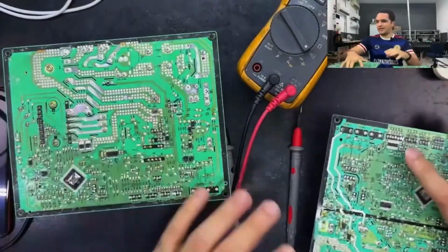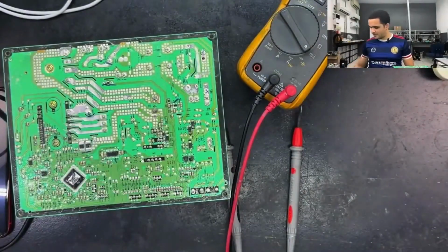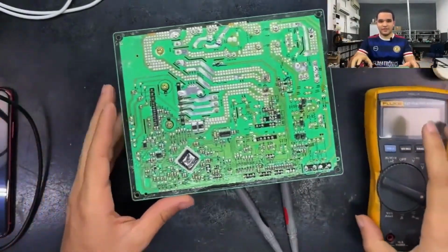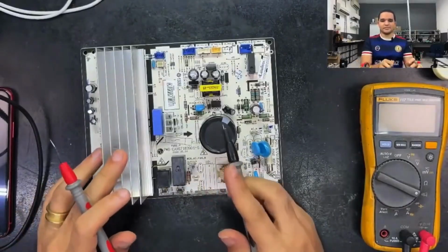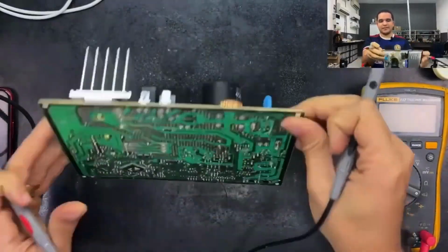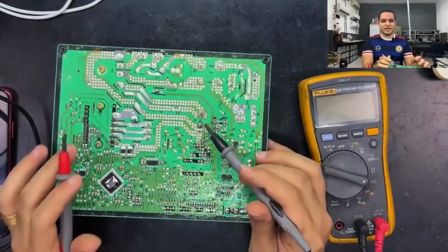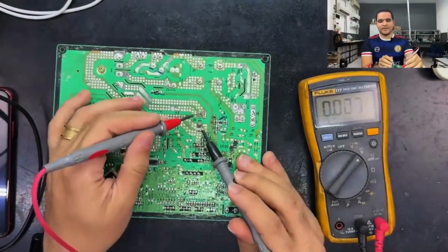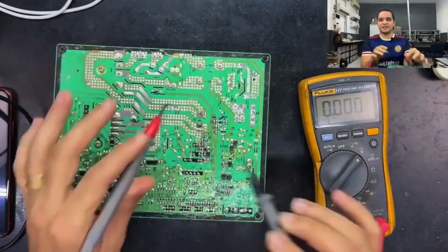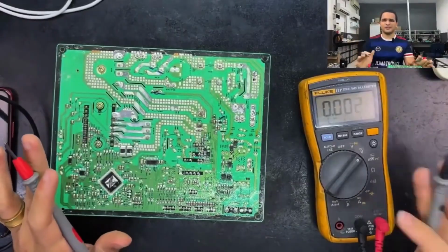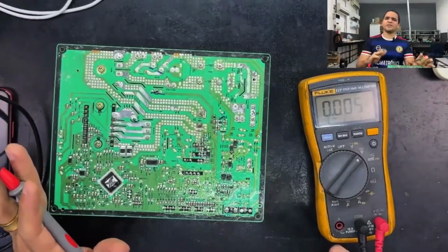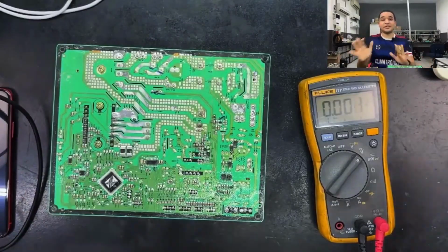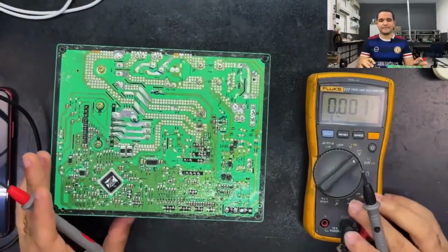I'll begin first with this smaller board of the dual inverter. This is the capacitor you need to pay attention to. You generally access this board here, right? Flipped. So this voltage needs to be on this capacitor. You'll measure as the voltage scale goes down. Here it won't show anything. Carefully measure that it needs to be between 280 and 310. Work within this range, okay?